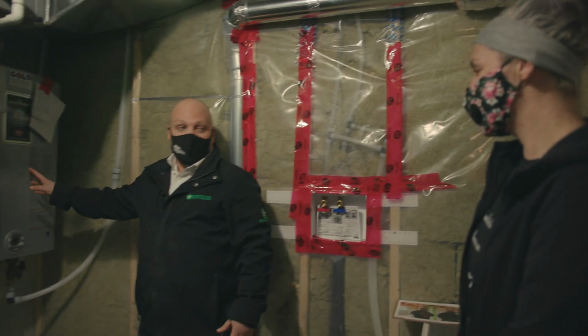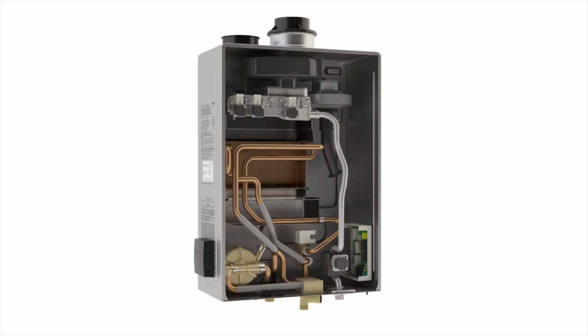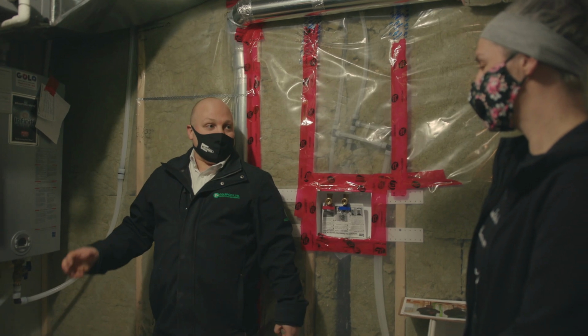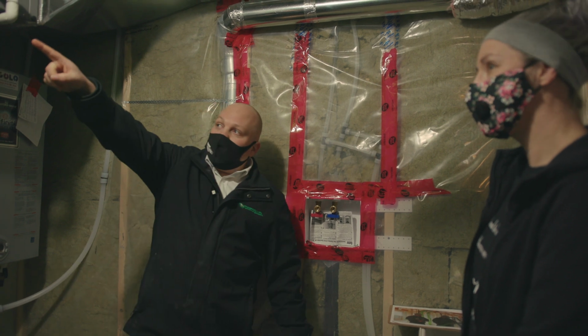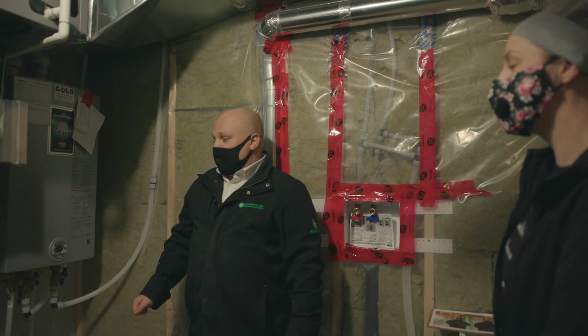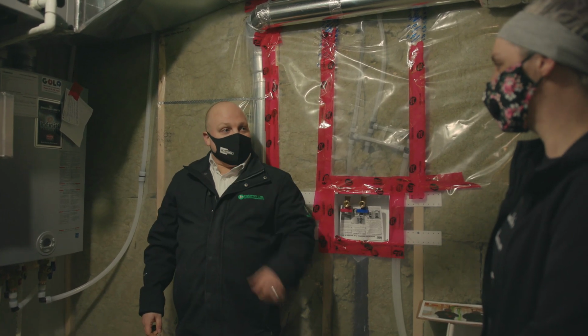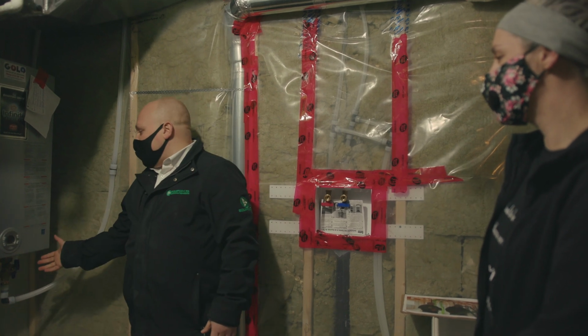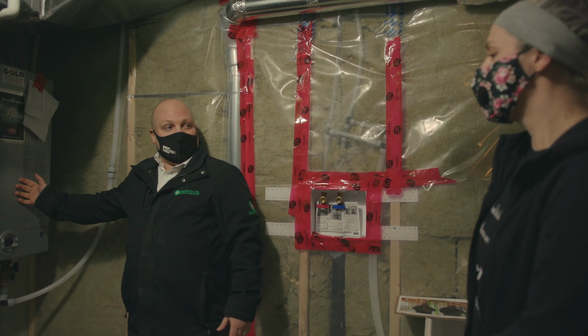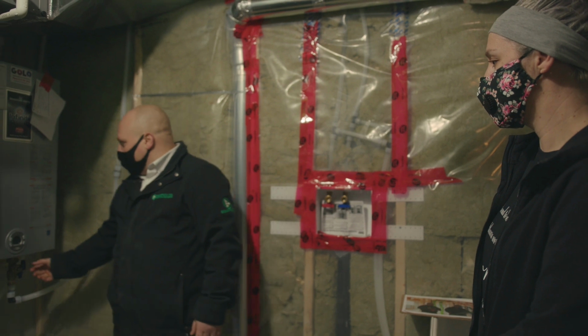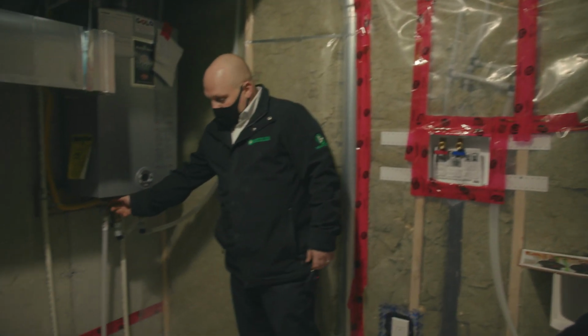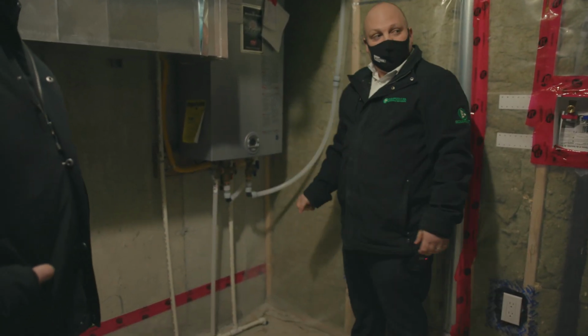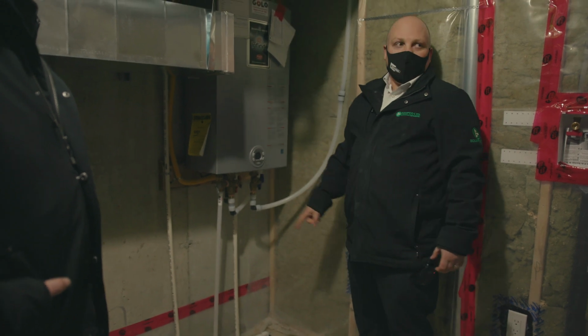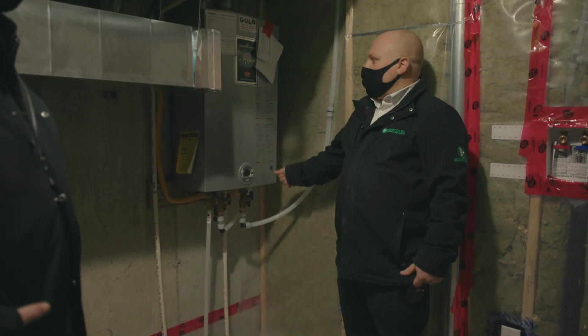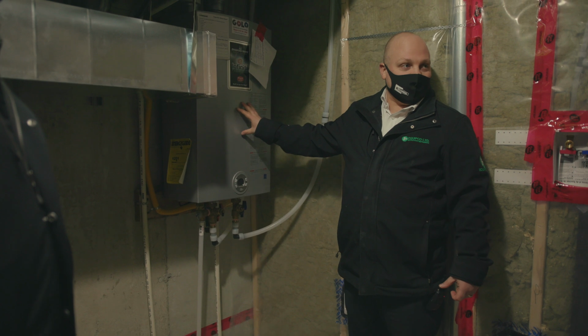Tankless water heaters are great, and it's a technology that's fast growing in popularity. One main thing you want to do on a tankless water heater is once a year, call that number right up there and say, hey, it's springtime, can you come in and do a flush of my tankless water heater? What they're going to do is hook up a hose down here, hook it up here, put it into that drain, and run vinegar or some sort of chemical through it to clean the heat exchanger inside.